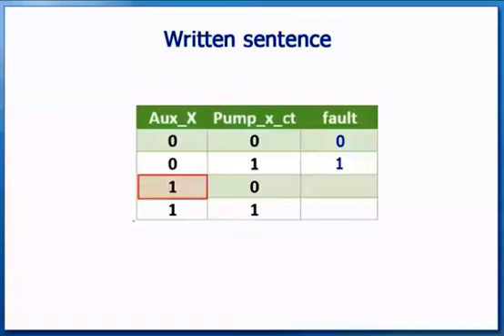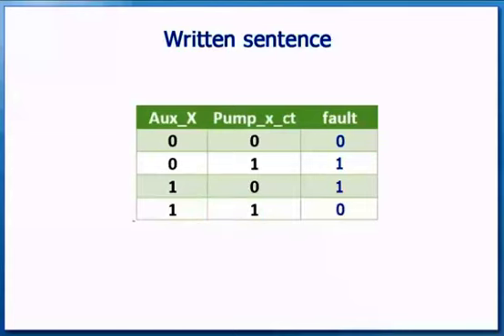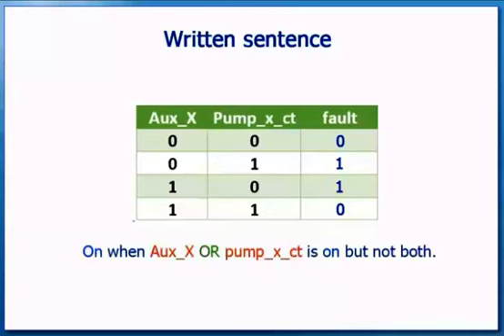If auxiliary X is on and PUMPXCT is off, then this is a fault — we show a 1. If auxiliary X is on and PUMPXCT is on, then this isn't a fault — we show a 0. Fault is on when auxiliary X OR PUMPXCT is on, but not both. You may recognise this truth table as the exclusive OR.